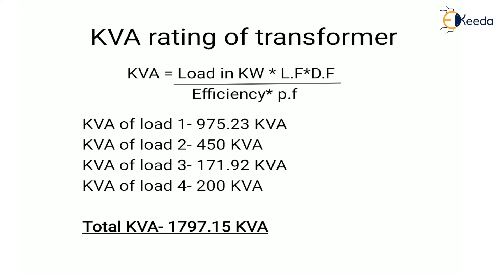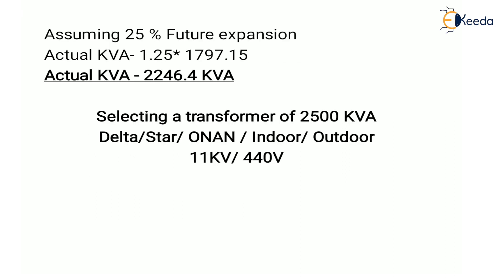Next, we have to assume future expansion because the load on the transformer may increase in the future, and it should be capable of handling that additional load. Assuming 25% future expansion and taking 25% of total KVA, we get the actual KVA value of 2246.4 KVA.